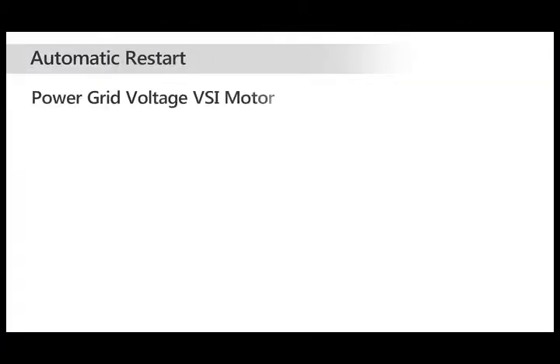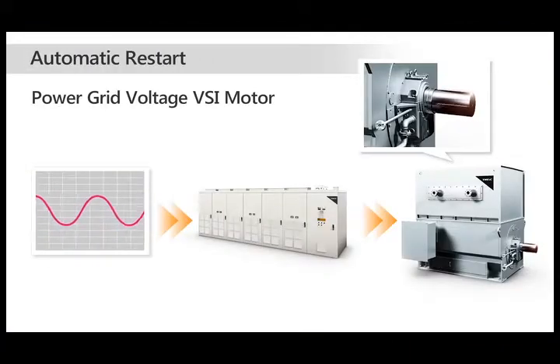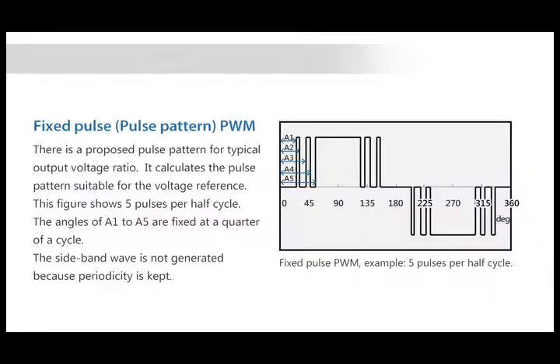In order to make PDS more stable and reliable, we provide technical solutions. The power grid may not be stable, and sometimes instantaneous voltage dips may occur. Ride-through control or automatic restart function is provided as standard functionality to minimize the decrease in compressor speed. Restart is available for power recovery within 2 seconds as your project requires.